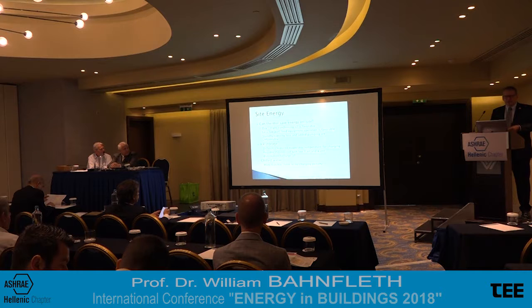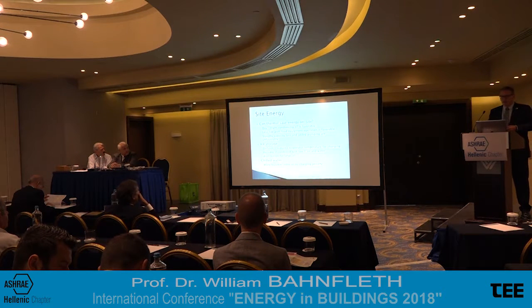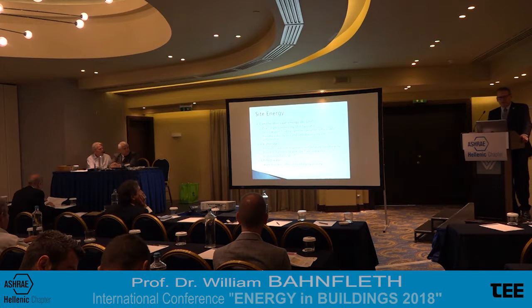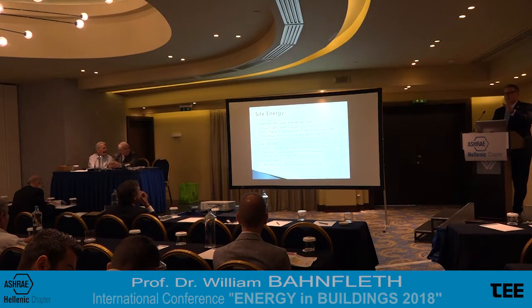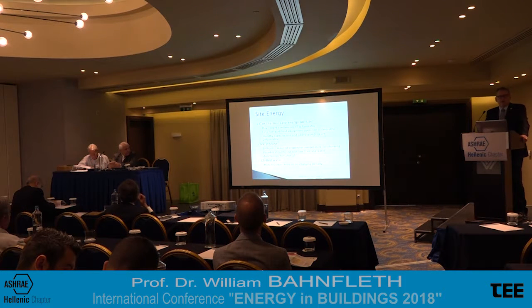So let's look at the issue of site energy, and we'll look at this with a very simple example of only one day. You have to imagine that this sort of effect that I'm going to show here could be carried over from day to day and would actually result in an aggregate savings. So one of the main things that happens with thermal storage when you move the production time from on peak, when it would have been needed to meet the peak load, to off peak, is there should be some improvement in condensing temperature. And for air-cooled systems in particular, the day to night condensing temperature difference can be quite significant.